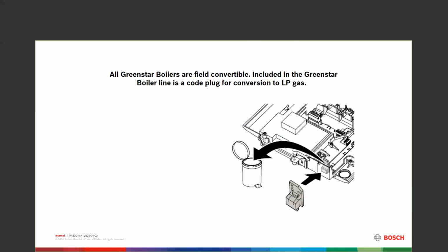That code plug not only converts from natural to LP, but it also tells the control which boiler it is. So whether it's a heat only, whether it's a 57, a 100, a 131, a 151, whatever it happens to be, and whether it's a combi or a heat, it tells that control all of those, because the controls are all the same for the different boilers, and they don't know what they are without that code plug. So you are determining what that is. Check the number on the code plug, make sure it matches what you're supposed to have, that somebody didn't put the wrong code plug in the package or something to that effect, but just do a little bit of that.